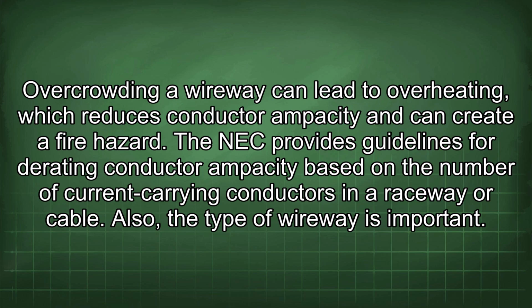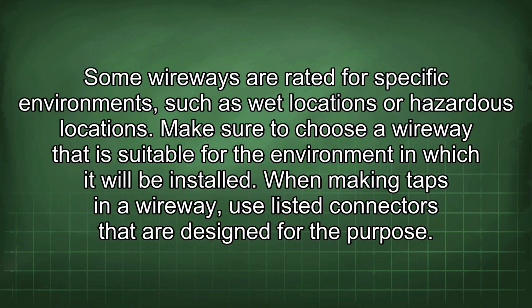The NEC provides guidelines for derating conductor ampacity based on the number of current-carrying conductors in a raceway or cable. Also, the type of wireway is important. Some wireways are rated for specific environments, such as wet locations or hazardous locations. Make sure to choose a wireway that is suitable for the environment in which it will be installed.